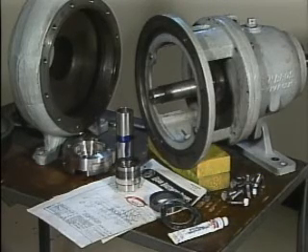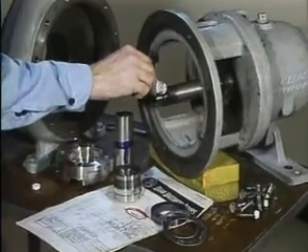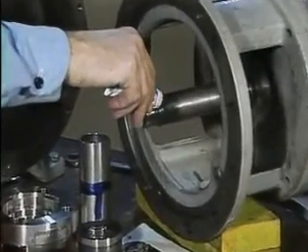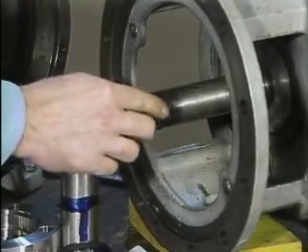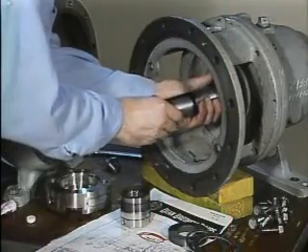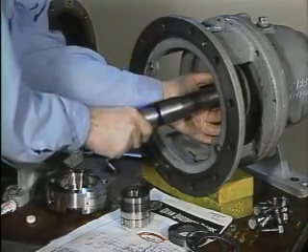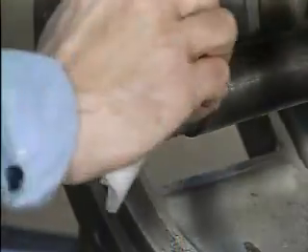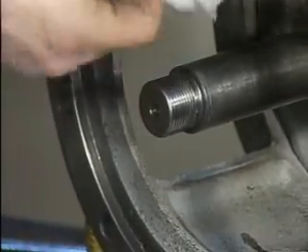But some pumps rely on metal-to-metal contact instead of a gasket or an O-ring to seal between the shaft shoulder and the sleeve. On these pumps, the surfaces should be lapped to remove imperfections that could interfere with creating an acceptable seal. To do this, the shaft key is removed and then lapping compound is applied to the shaft shoulder. Next, the sleeve is placed on the shaft and turned. After several minutes, the sleeve is taken off and the lapping compound is cleaned away. The surfaces are then inspected to make sure that proper surface contact can be made.